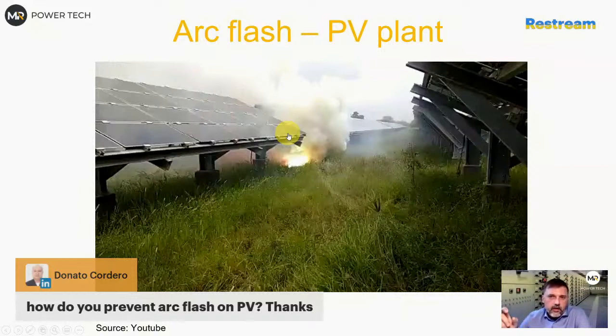Generally the idea, as far as I see in PV, is that the MC4 connector is a problem, which sometimes overheats and has a serious arc. Usually it's not an arc flash phase to ground or phase to phase. Usually it's in series on the same phase because of overload, whatever. There's like goats, sometimes there's a lot of animals around.